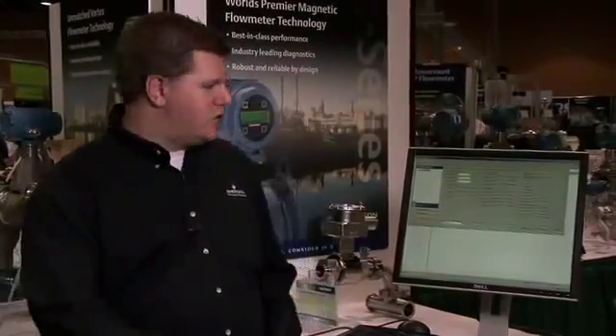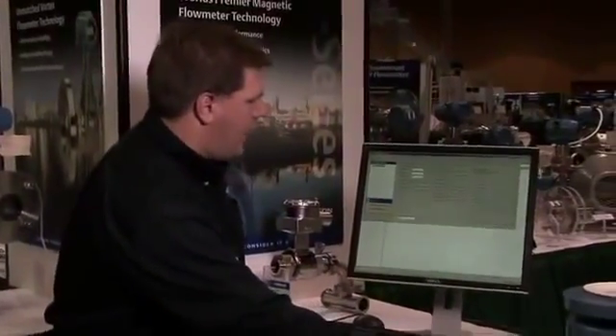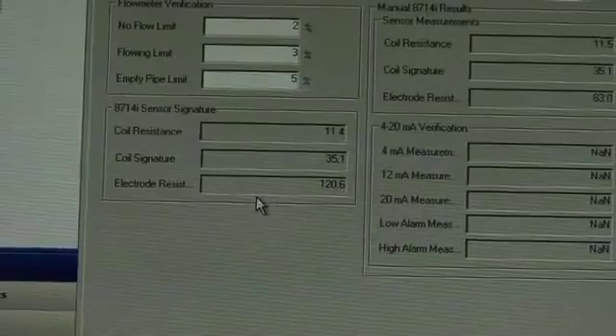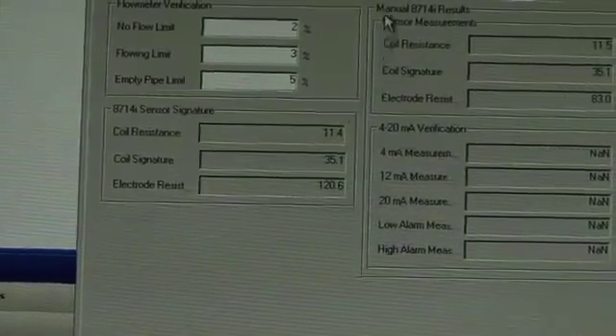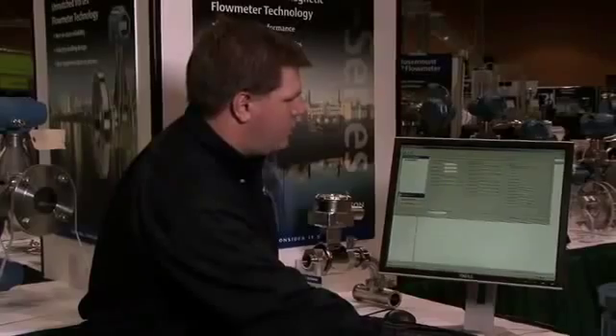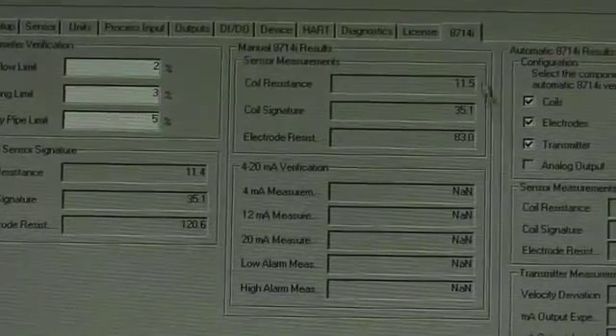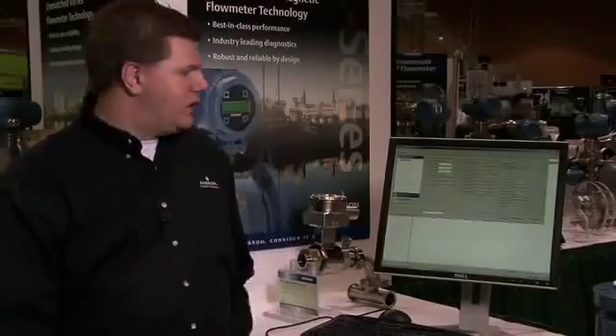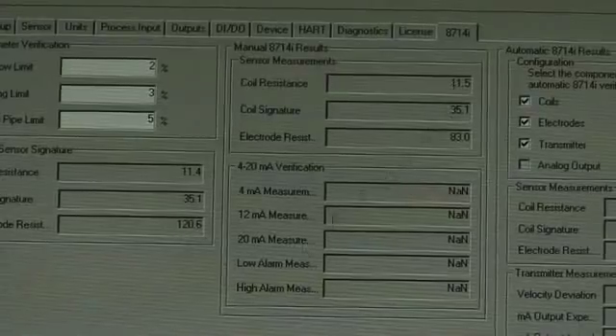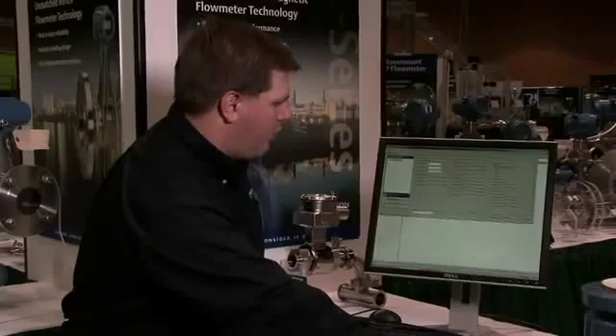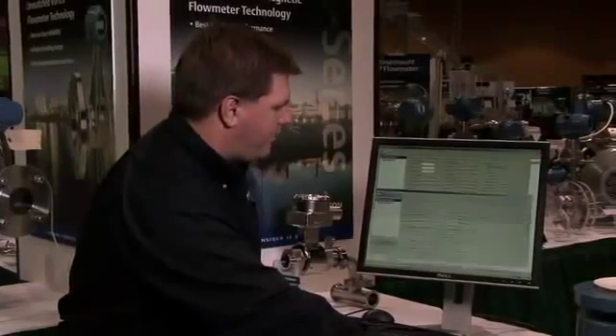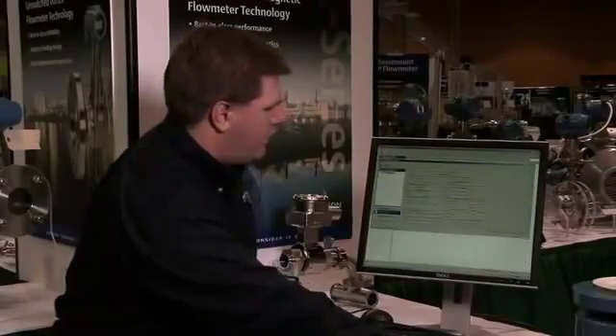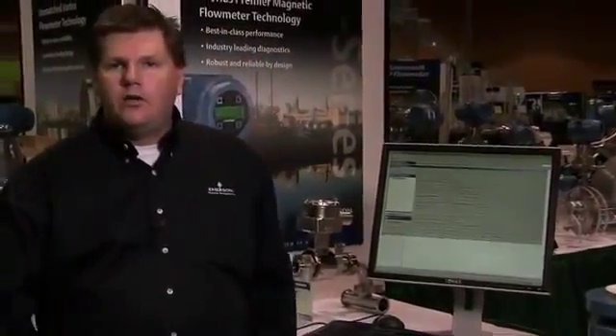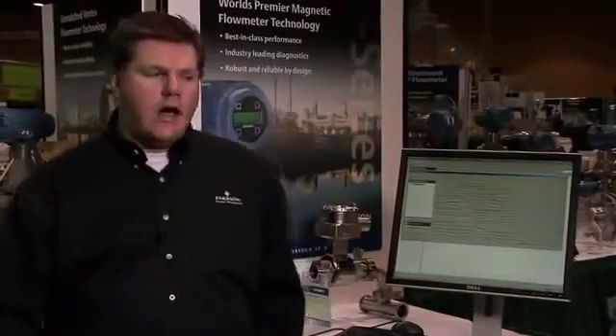Let's take a look at how this meter verification technology looks inside of our AMS system and how it can benefit you as the user. Like we discussed, at the factory, baseline measurements are taken and stored in the non-volatile memory of the transmitter. With the on-demand system, the transmitter will go out and manually measure those same values and do a comparison of those diagnostic values, the measurements to the sensor signature, and it will populate a report that you can then use to file with the instrument file or submit to the auditor.